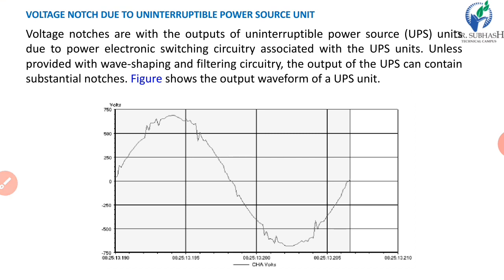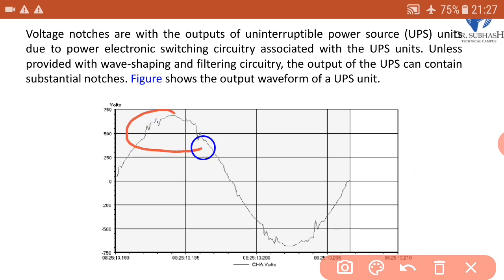Voltage notch due to an uninterruptible power source unit, or UPS unit. Now we have to define what a notch is. A notch is a periodic disturbance. It means if we see a disturbance here, then in the negative half cycle also we can see this type of disturbance. So it is periodic in nature. Voltage notches appear at the outputs of uninterruptible power source units due to the power electronic switching circuitry associated with the UPS units. Unless provided with wave shaping and filtering circuitry, the output of a UPS can contain substantial notches. So this is the typical waveform for the UPS unit.